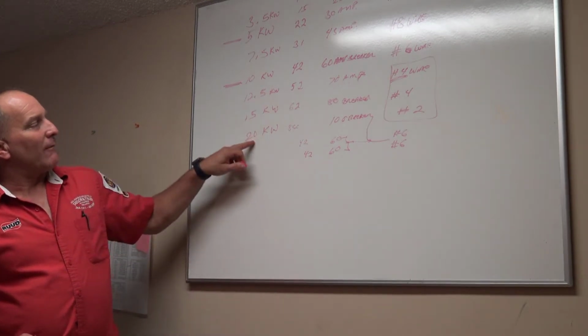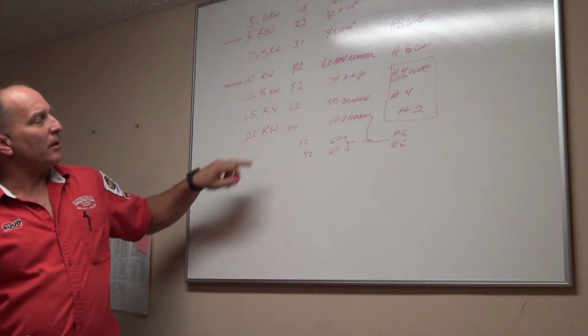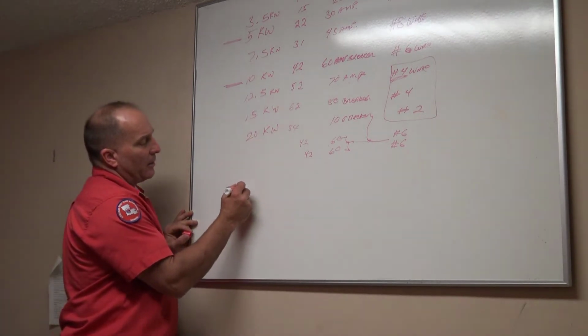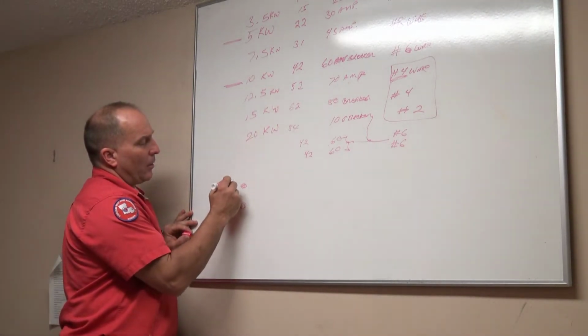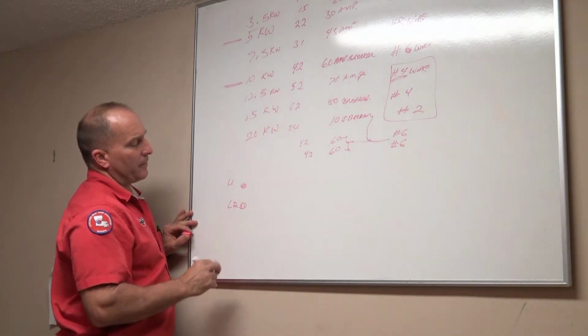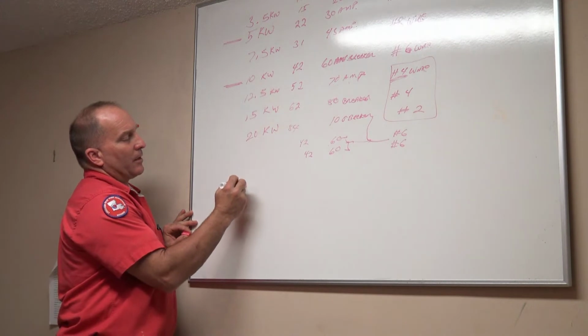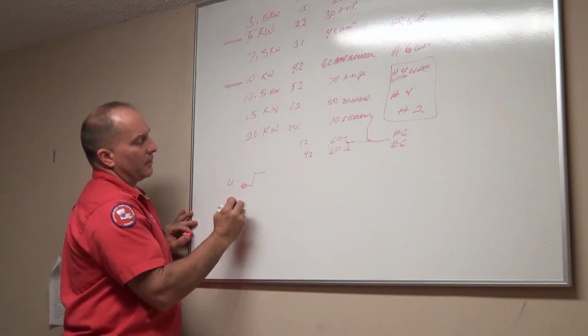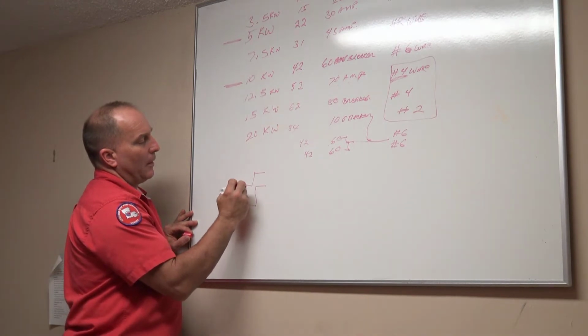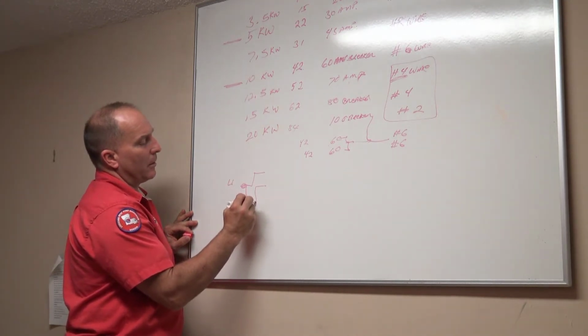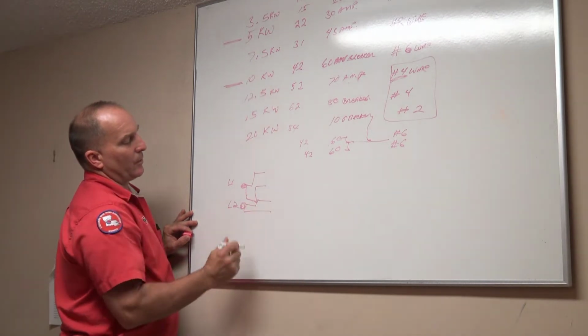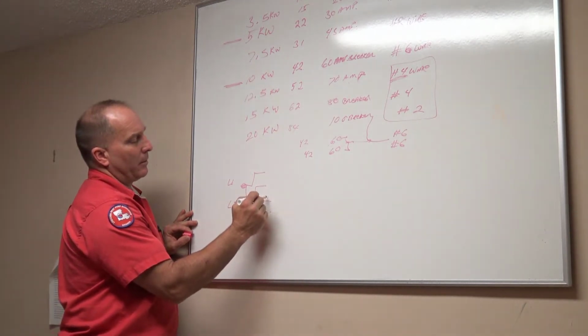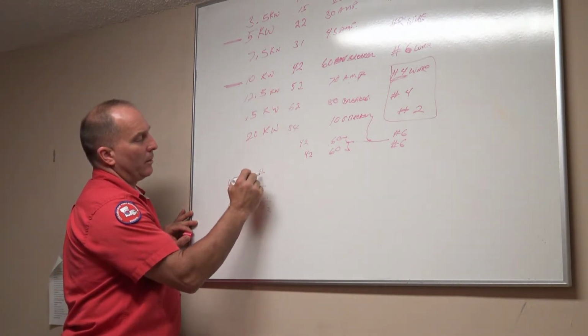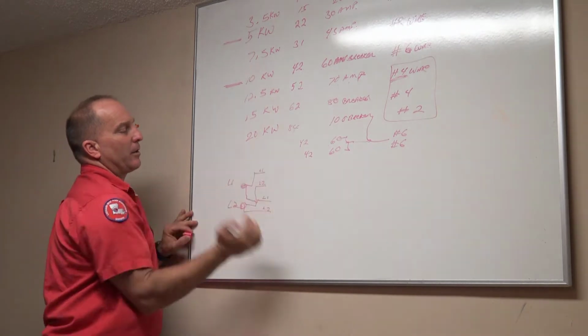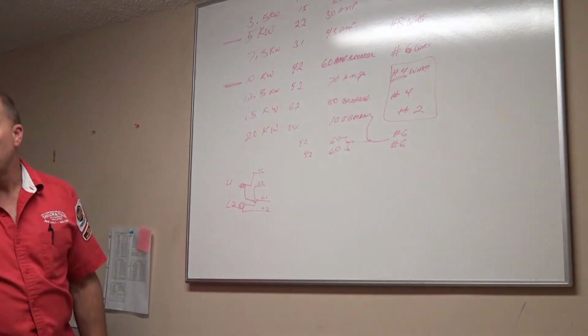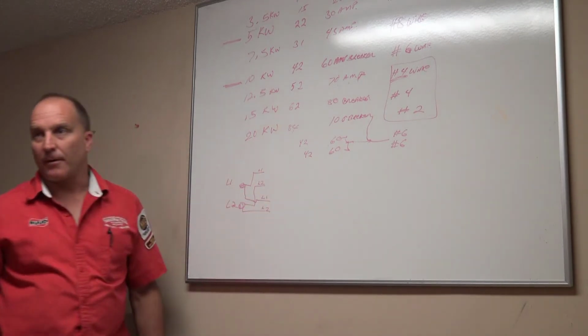Now, if you have one 100 amp breaker feeding 20 kW, then you would have this terminal, L1, L2, okay? Then this would come up like this, and this would come down like this. I'll jump that over. So now I have an L1, L2, L1, L2, and then my breakers go into there. 2 60 amp breakers. And then it can go into the system from there.